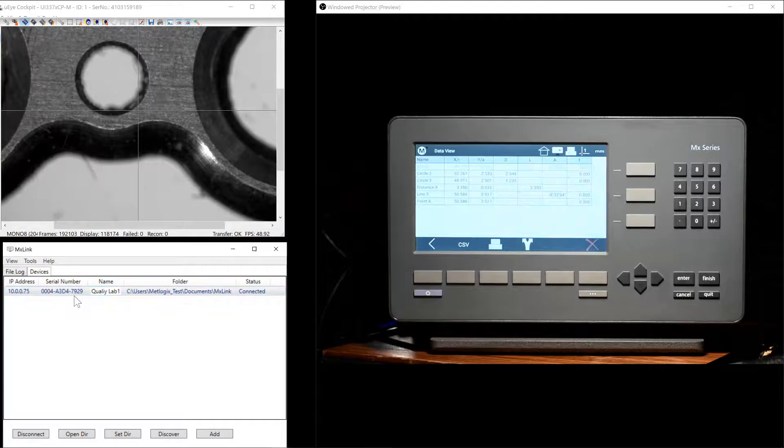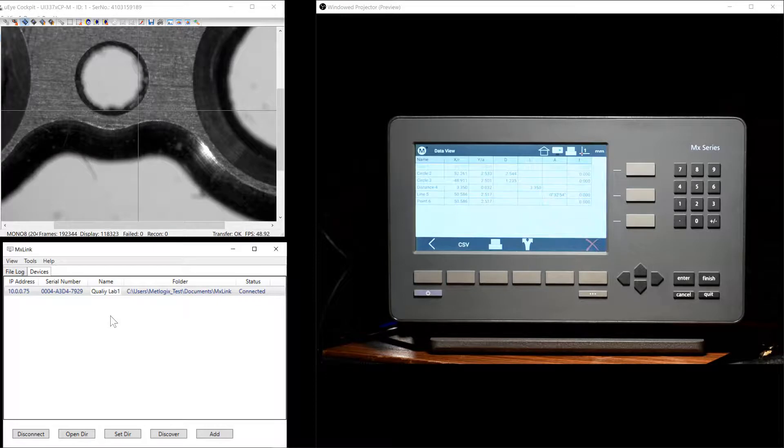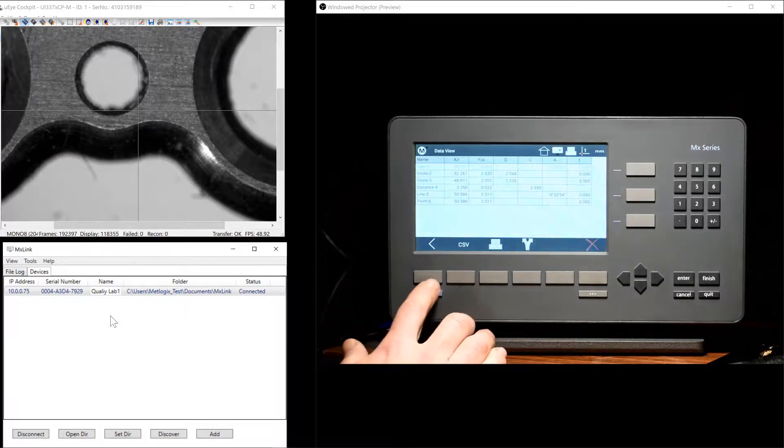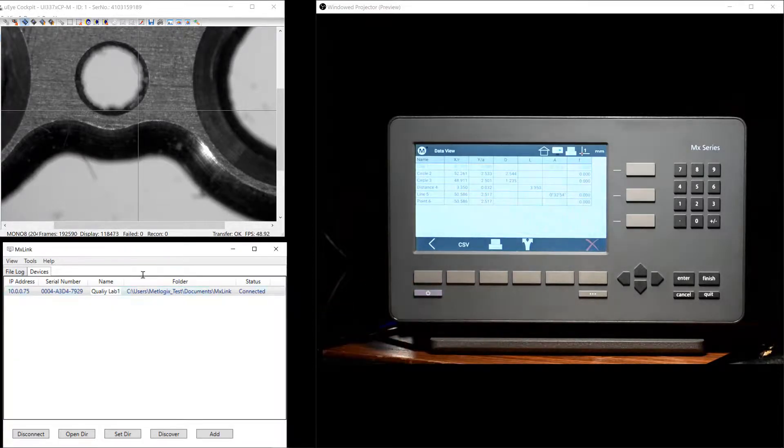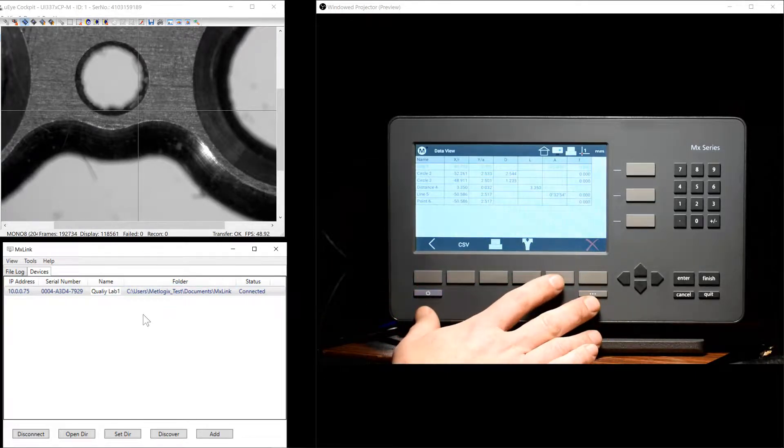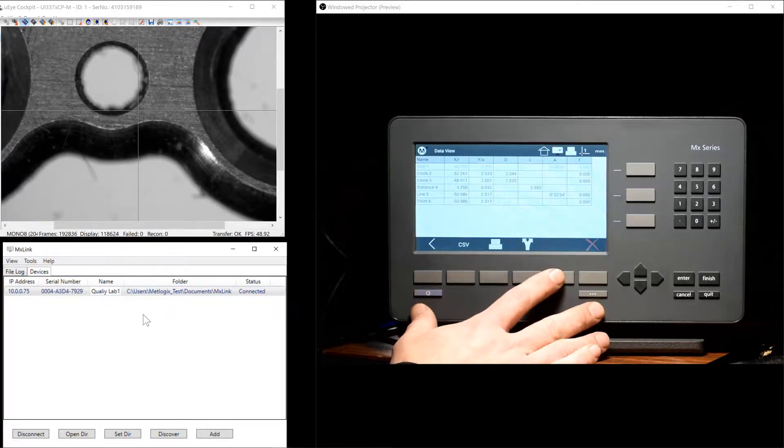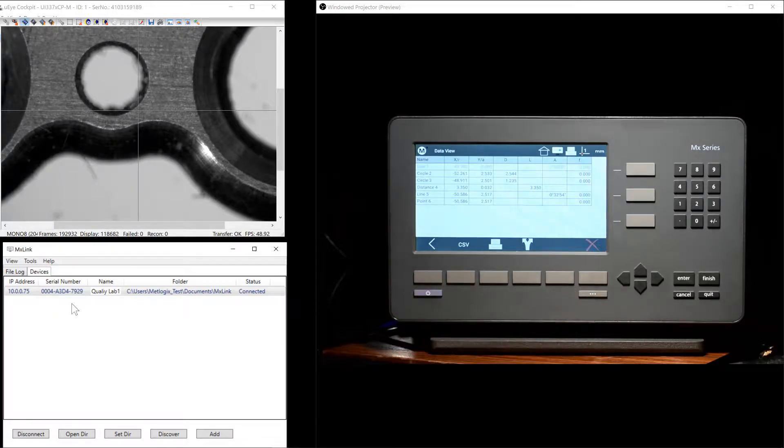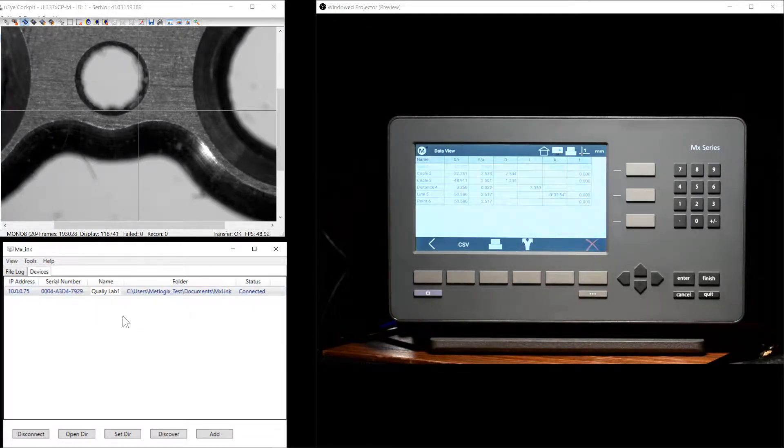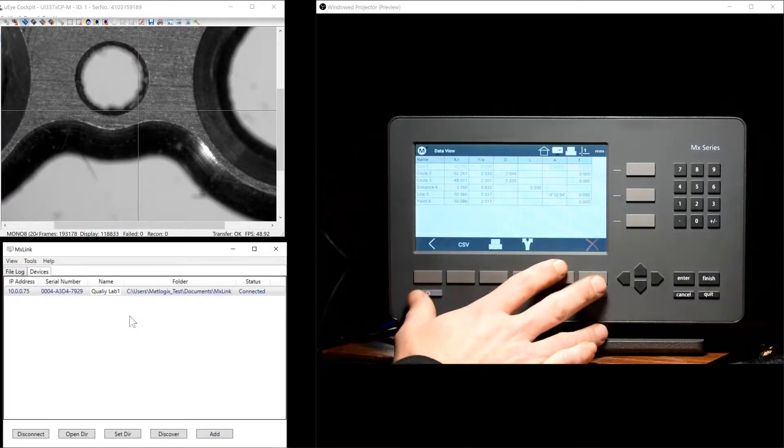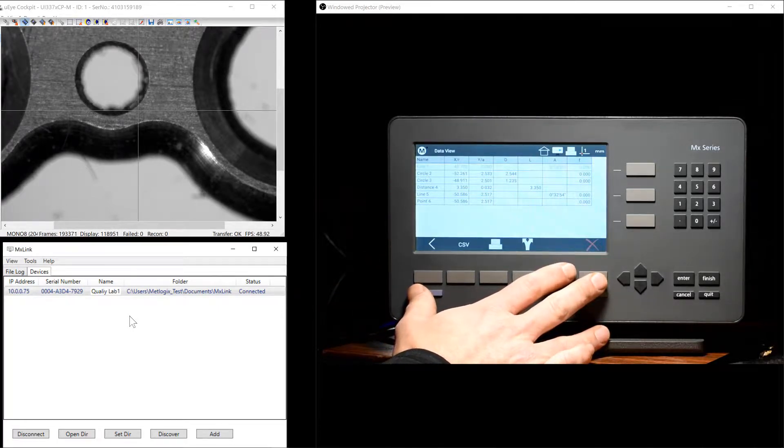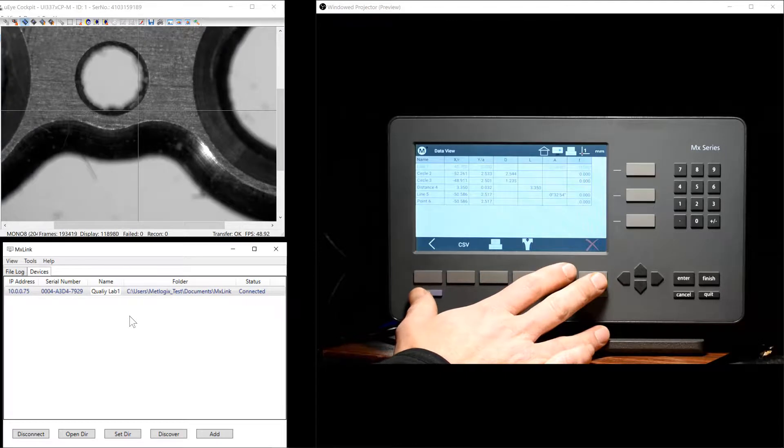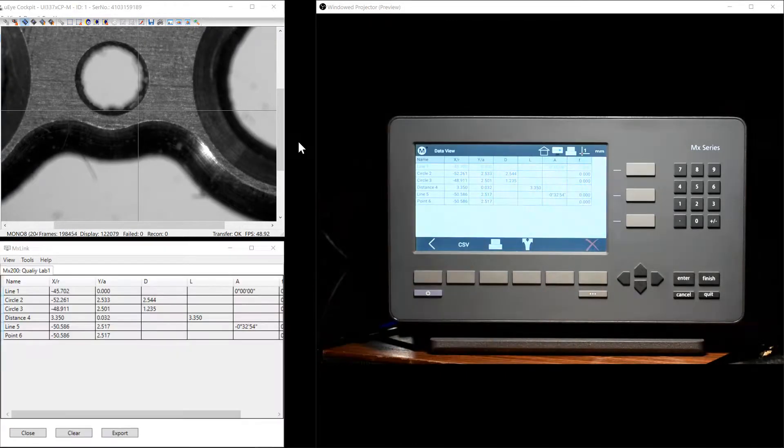It is possible to configure the MXLink to communicate with more than one device. There are two ways in which this works. Either a single instance of the MXLink can be connected to multiple licensed MX200s, or multiple instances of the MXLink application can receive data from a single MX200 device, whichever better meets your data management requirements.